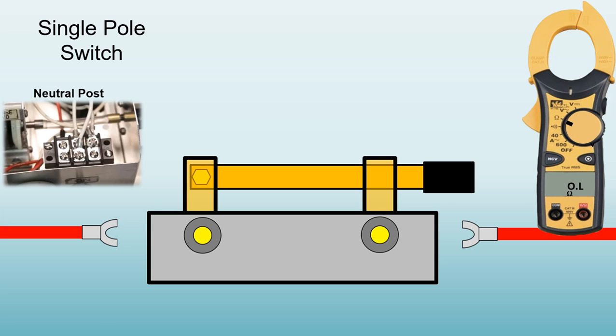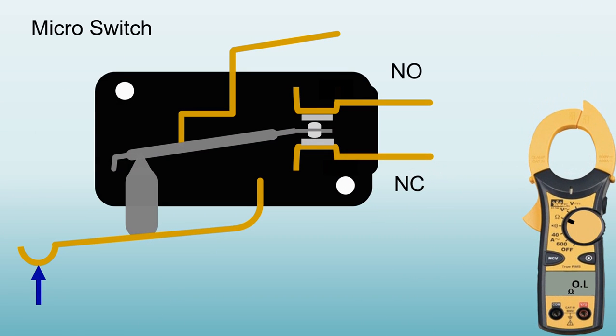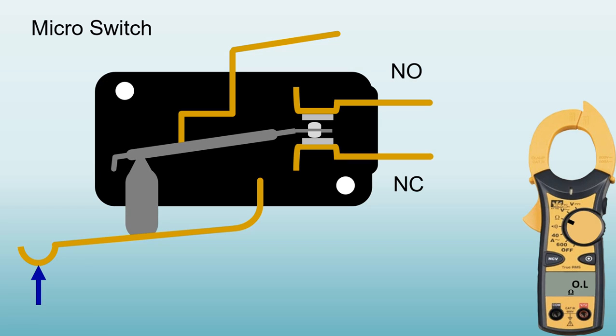To test continuity on a single pole switch, again, we turn power off to the system. You would remove your wiring from the device or the switch that you wish to test. Set your voltmeter to read ohms or to audible continuity. Place your meter leads between the connections, and this shows that you have a complete connection and the circuit is good. This tells you that your switch is working.